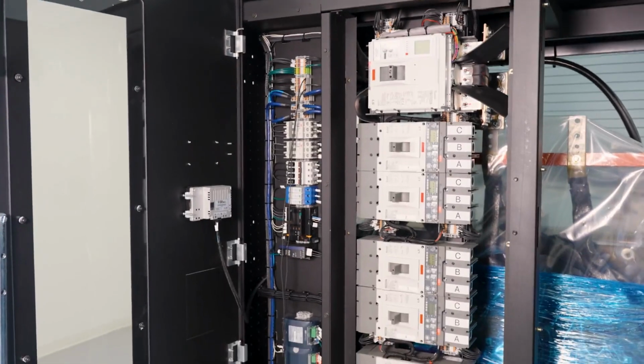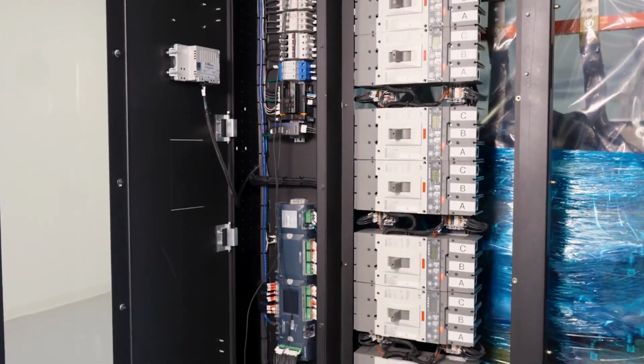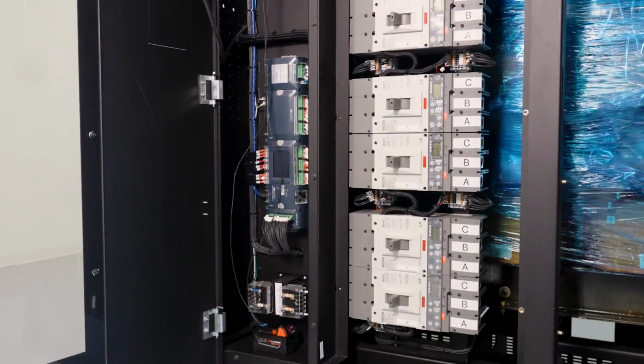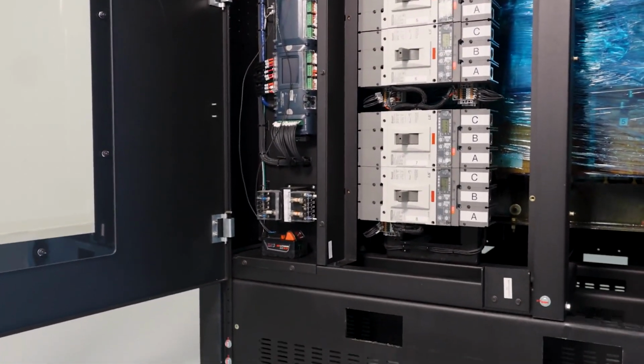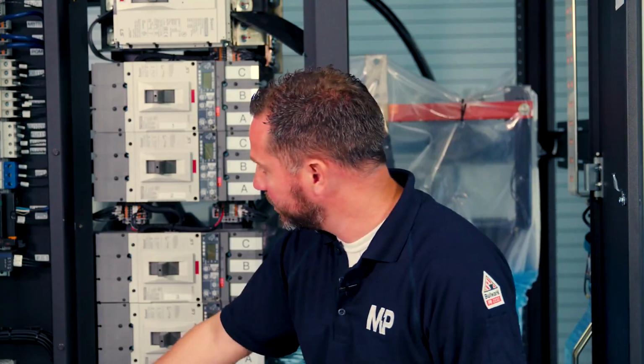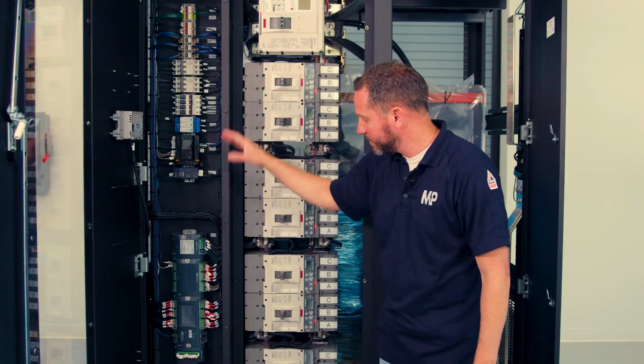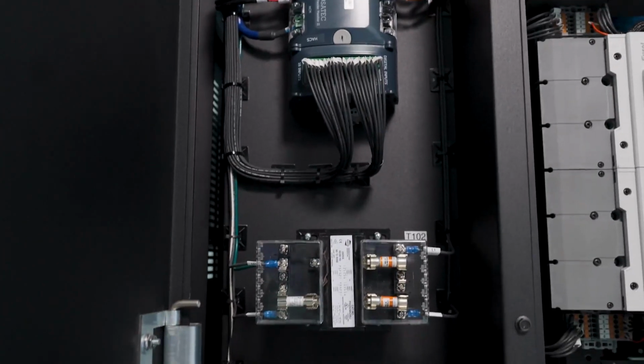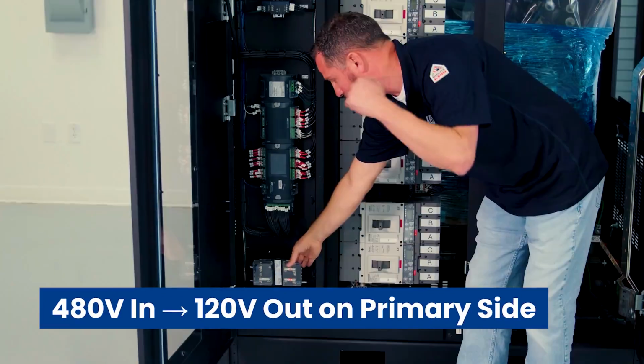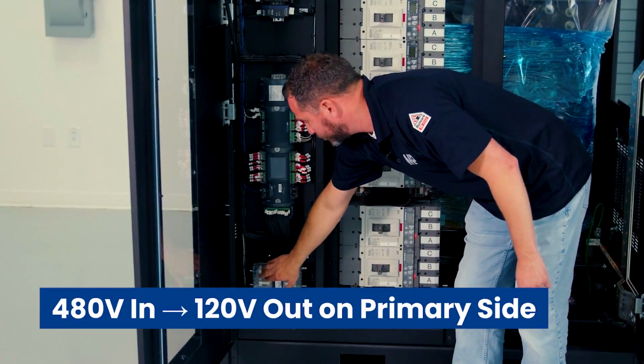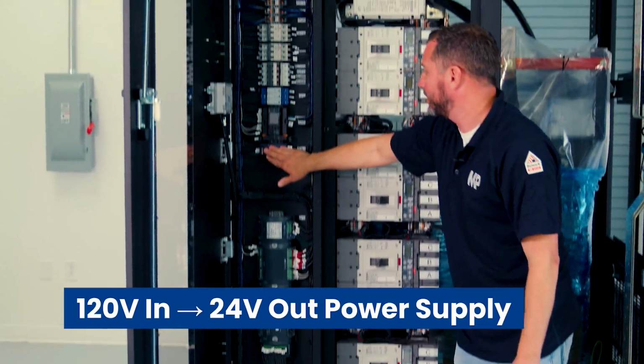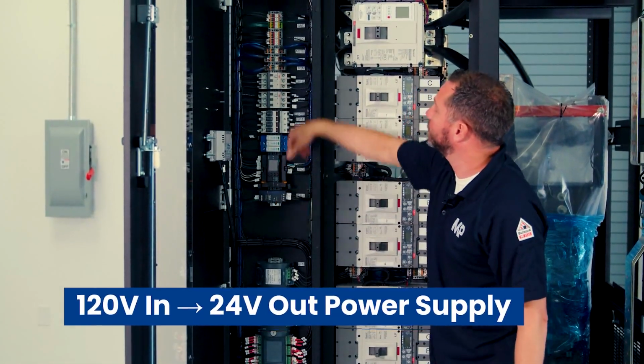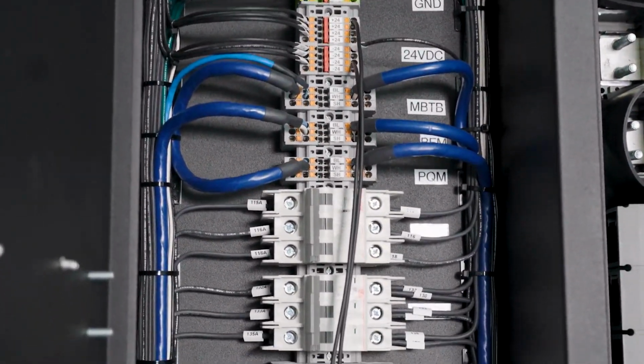For our controls, we have our 3 main components. Our Modbus is communicating with all these components, and the customer will communicate with this through a serial, through our HMI, and they can also plug into our BFM and our PQM to see all the information there as well. We have our 480 volt coming in, tapped on our primary side, with our 120 coming out, feeding up to our 120 volt supply with our 24 volt, and all that is fed up through our terminal blocks up top.